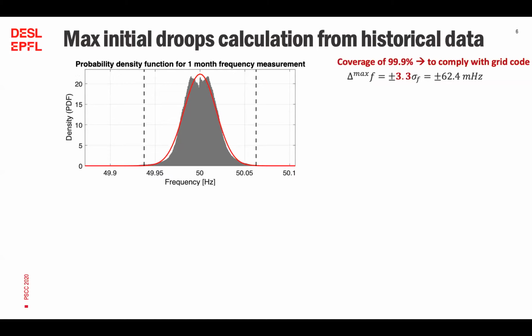grid in our campus. In particular, on the one hand, we have considered the maximum deviation of the frequency from the 50 Hertz reference value, taking place with a standard deviation factor of 3.3, meaning that only in 0.1% of the cases we will be experiencing the maximum deviation of frequency, thus the maximum corresponding provision of active power.